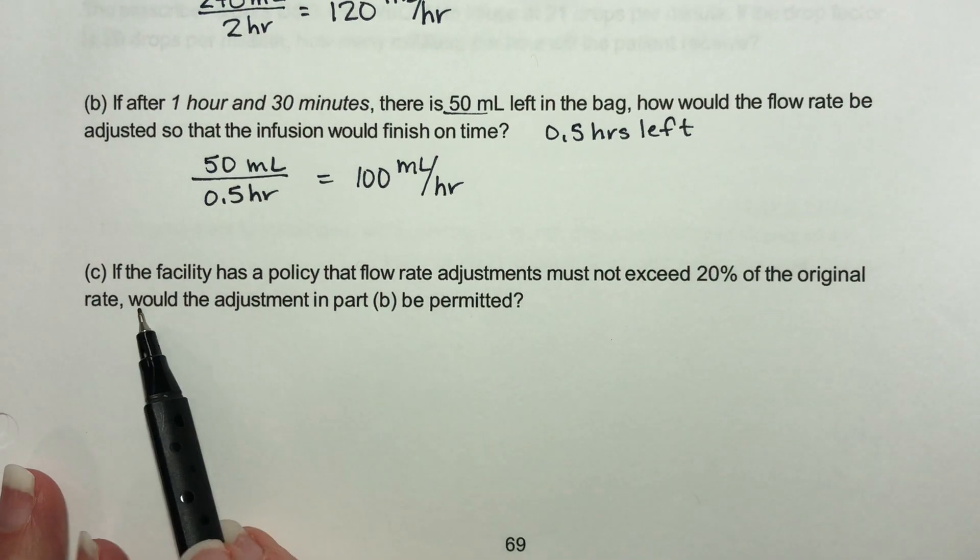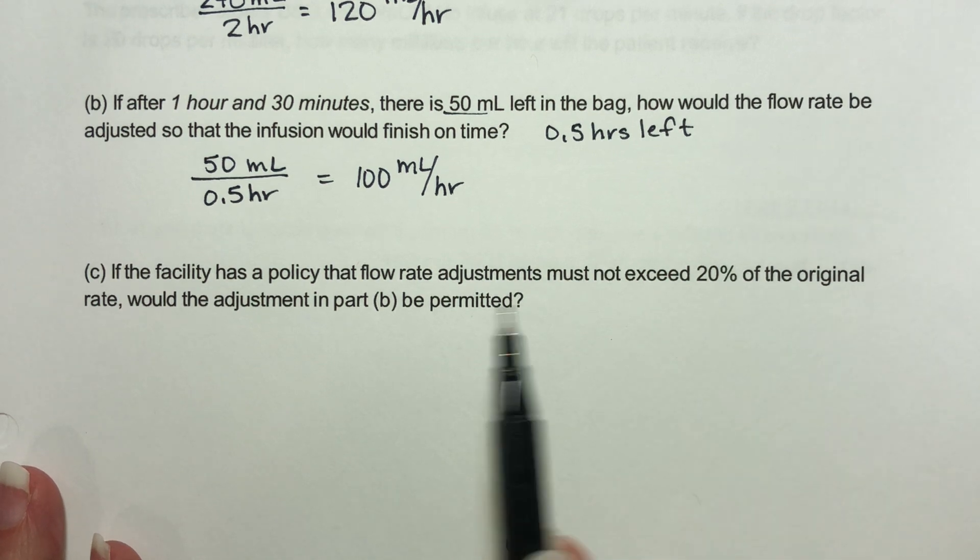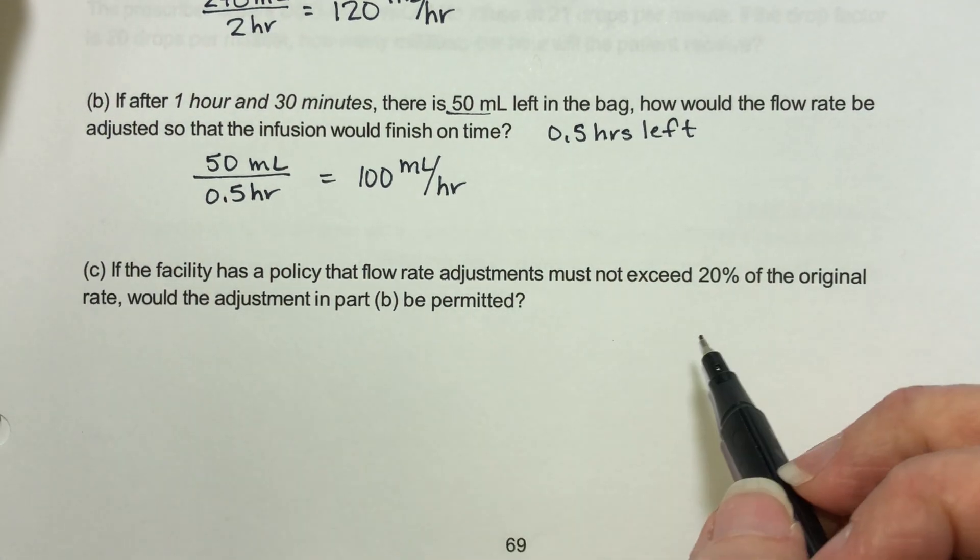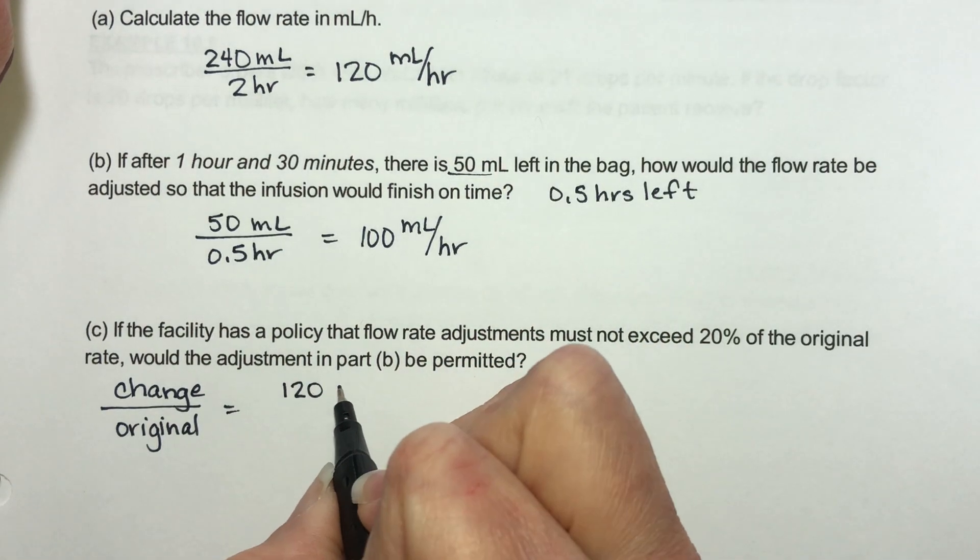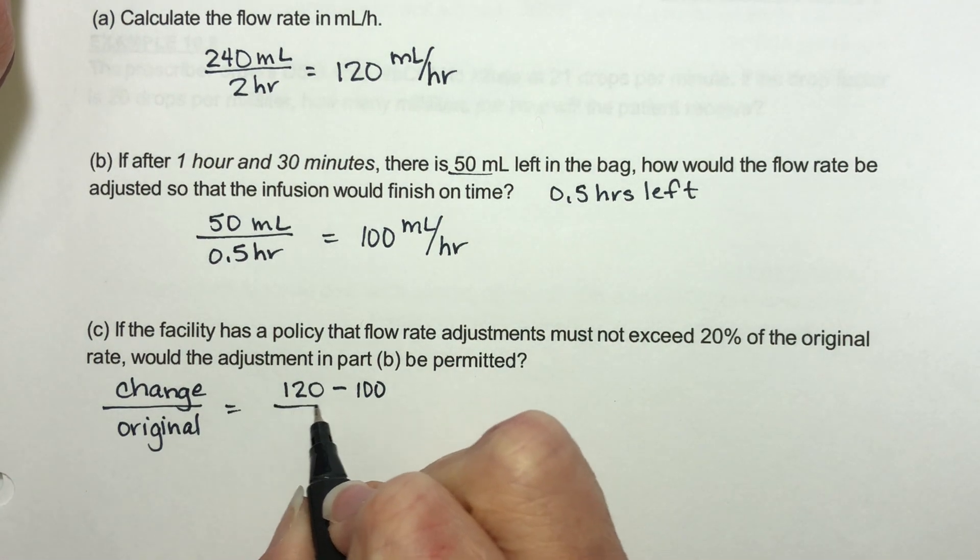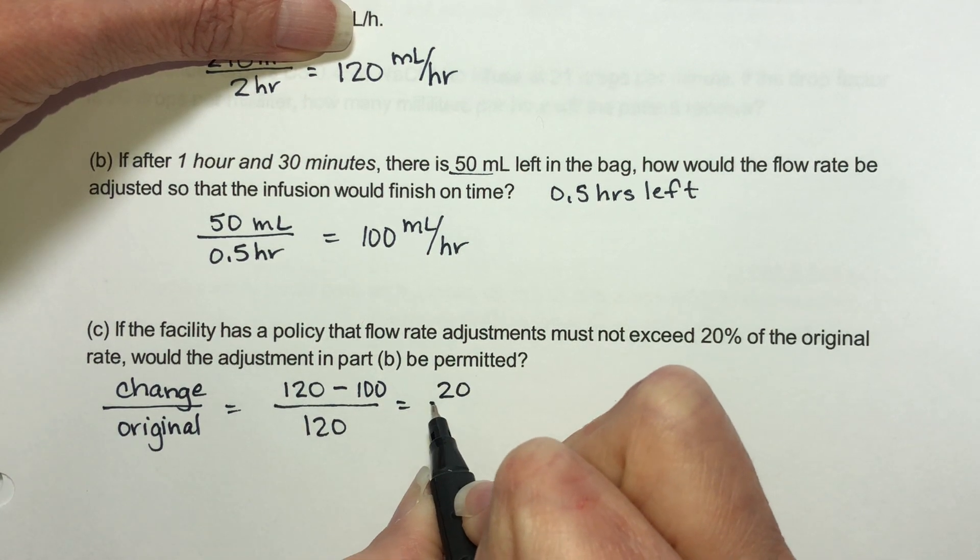Now, if your facility has a policy that flow rate adjustments must not exceed 20% of the original rate, would this adjustment be permitted? Early on in the class, we talked about percent increases and percent decreases. And what we look for is the change over the original. So to find the change, we're going to just subtract. I was at 120 and I changed to 100. So that's going to be a change of 20. The original flow rate was 120. So this is 20 over 120.